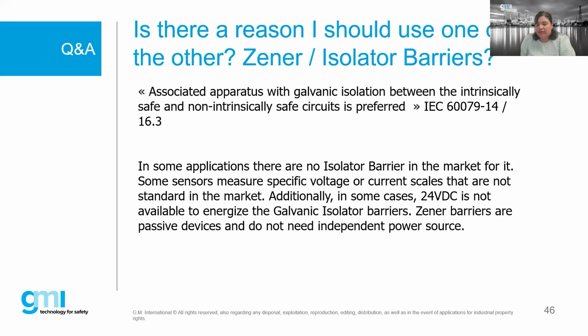Bobby touched on a very interesting point there, as well as that multi-channel option. Usually galvanic isolator barriers also have signal conditioning on them, so you're able to get, let's say, a thermocouple to 4-to-20 conversion on that one device. So it does these conversions, or has built-in dry contacts for alarms, or can do some multiplexing requirements on it. So galvanic isolator barriers will often have signal conditioning you could take advantage of if your design allows it.